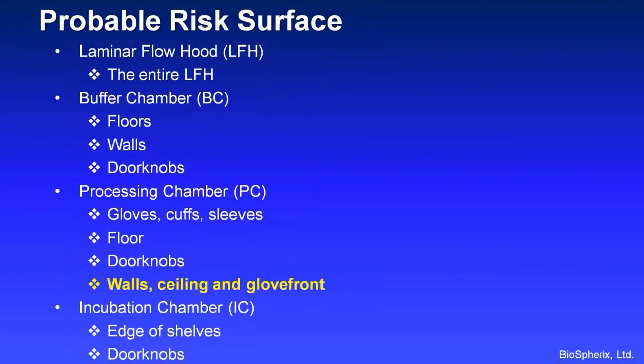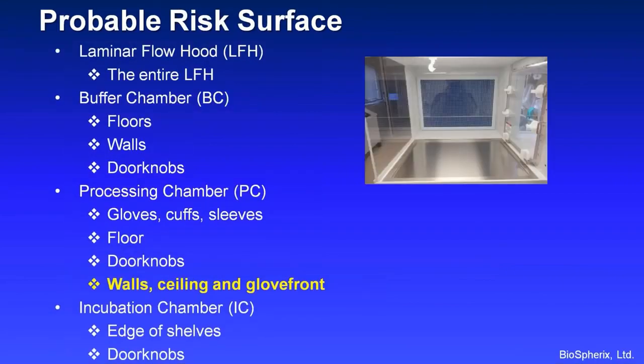Also, it is not necessary to disinfect all surfaces on a daily basis. The only thing you need to wipe is the probable risk surfaces. For the Xvivo system, the entire laminar flow hood is considered a probable risk surface because it's open to the room and the personnel.